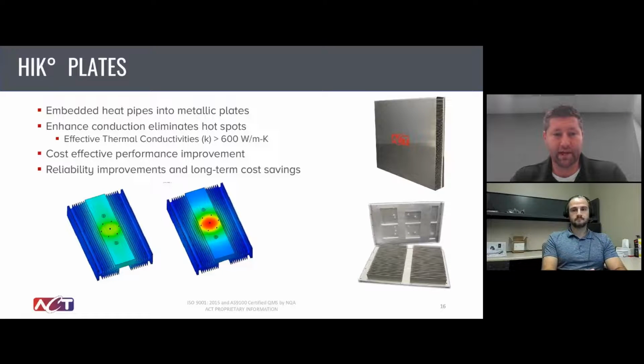An example of that is shown in the bottom left figure—a single metallic IGBT cooler, with a single IGBT mounted to the system. In this thermal model, we used the inputs on both the left and right: the right one was pure aluminum, and the left one was after it was integrated with heat pipes.